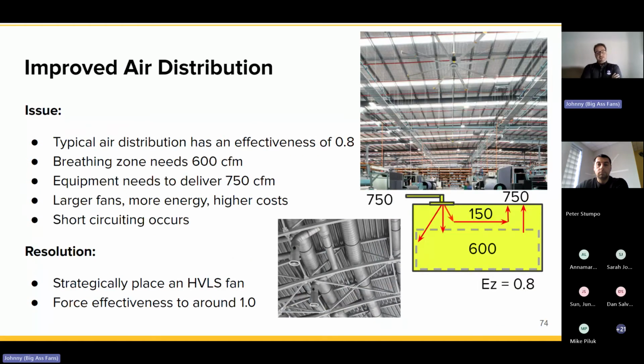Lastly, improved air distribution. When supplying air to a space, there's usually about an 80% effective rate between the CFM you're providing versus what's being exhausted and ultimately delivered to the occupied zone. With a fan, you can mix that air more effectively, so instead of accounting for that 80% factor, you can provide the appropriate amount of CFM, knowing the fan will mix it down to the occupied zone. You're not overcompensating on supply versus exhaust. These fans help mix the air and improve the existing systems already in place.